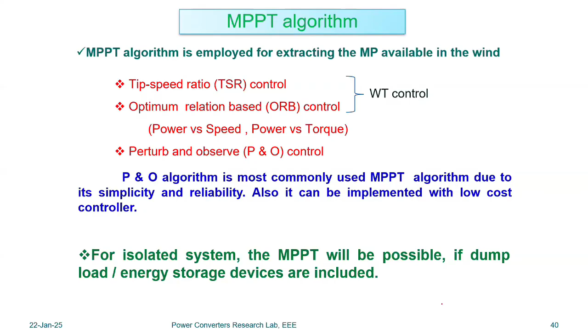The MPPT algorithm is employed for extracting the maximum power available in the wind. It is based on a mechanical or electrical parameter: tip speed ratio control, optimum relations based control, that is curve tracing from power versus speed, or we can have perturb and observe control. Most places use P and O, since it is very fast, simple and reliable. For an isolated system, MPPT is possible if a dump load or energy storage devices are included.